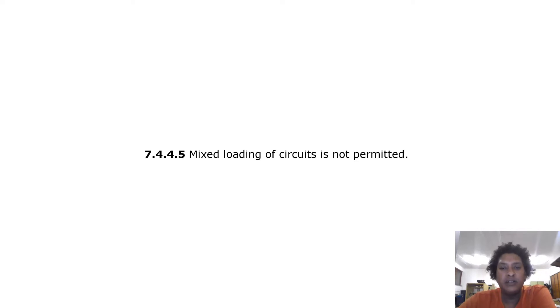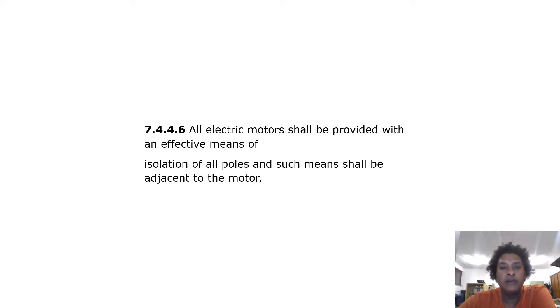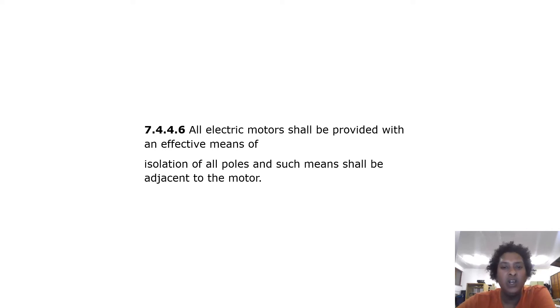Uninsulated live conductors are not permitted. Mixed loading of circuits is not permitted. All electric motors shall be provided with an effective means of isolation of all poles, and such means shall be adjacent to the motor.